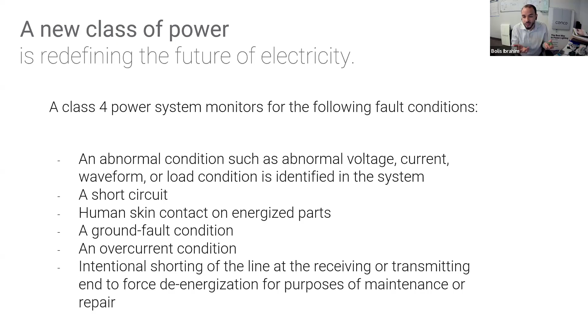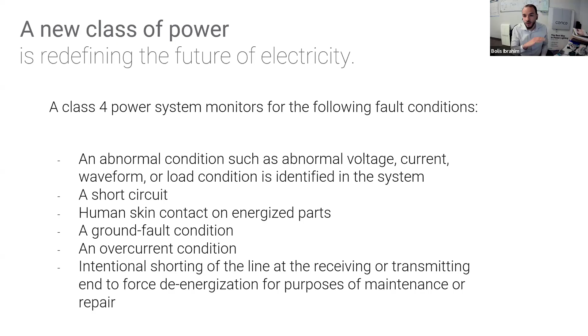So class 4 system, what does it do? It monitors abnormal conditions. It's basically a fancy circuit breaker. You can intentionally short circuit the system at 400 volts DC. Human skin, if you contact the parts by accident, you might feel it a little bit, but it'll shut off before it hurts you. So electrical shock is not a hazard. Ground faults, no hazard. Overcurrent, no hazard. And as I said, intentional shorting. They want it to be so safe that if someone is working on the system and they don't know if the system is energized, they have to be able to intentionally short circuit the system and ensure that the power shuts off. So it's pretty robust stuff.